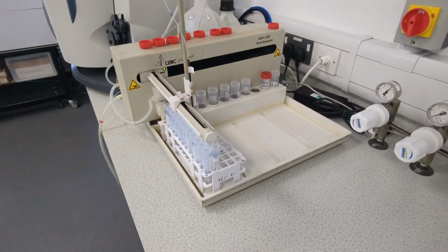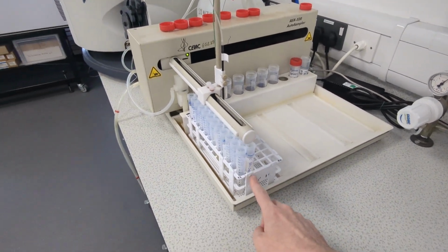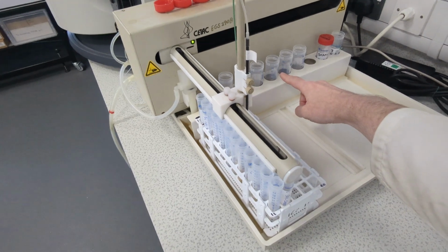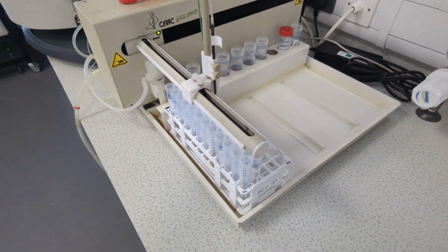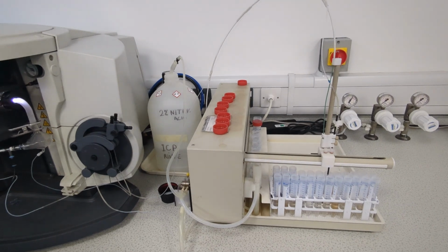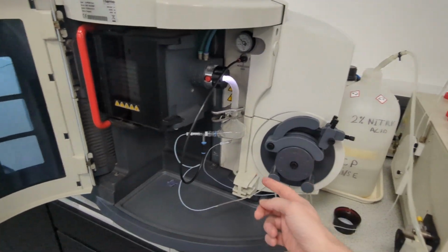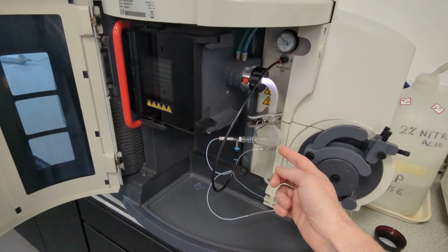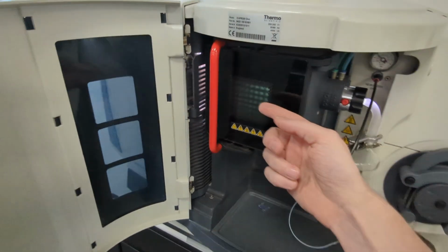This is the auto sampler. It contains 2 types of sample: our unknown samples, our extractions, and calibration solutions, which are used to accurately determine the concentrations of our unknown samples. Our samples are pumped by the auto sampler with the peristaltic pump through to the nebulizer and into the spray chamber. The finest mist in the sample is introduced to the plasma, where optical emission takes place.